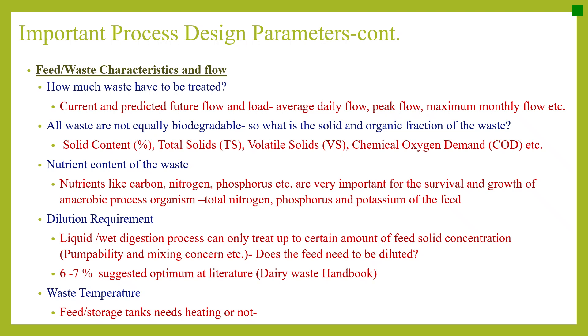Not all wastes are equally biodegradable, so we need information about the solid and organic fraction of the waste — solid content percentage, total solids, volatile solids, chemical oxygen demand, etc. Also, nutrient content of the waste is important. Nutrients like carbon, nitrogen, and phosphorus are very important for the survival and growth of anaerobic process organisms, so total nitrogen, phosphorus, and potassium of the feed must be known.